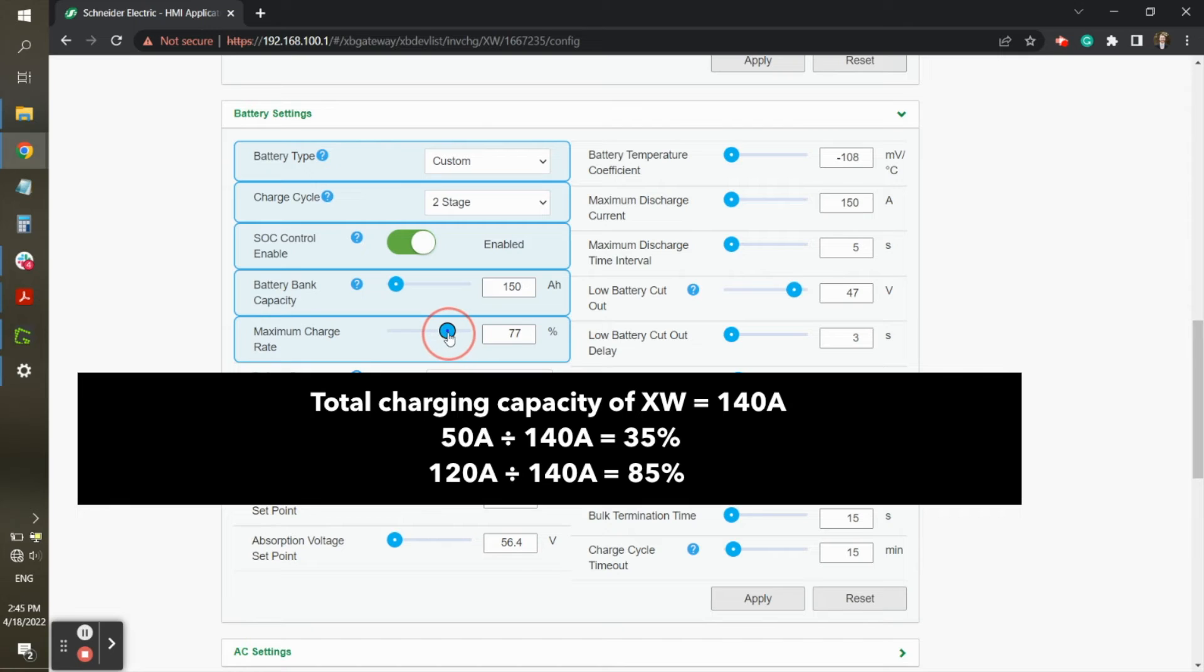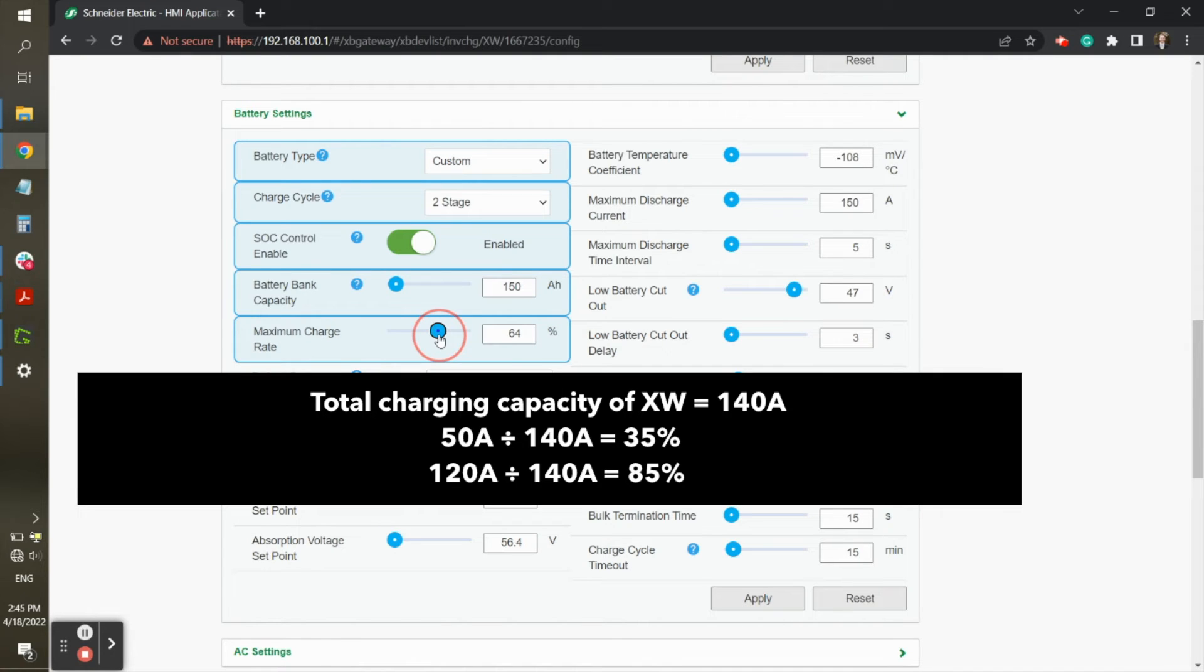Maximum charge rate is shown as a percentage. For the 10-year warranty, the charge rate should be set to 50 amps per HAB, or 35% of 140 amps. For the 7.5-year warranty, the charge rate should be set to 120 amps, or 85% of 140 amps.